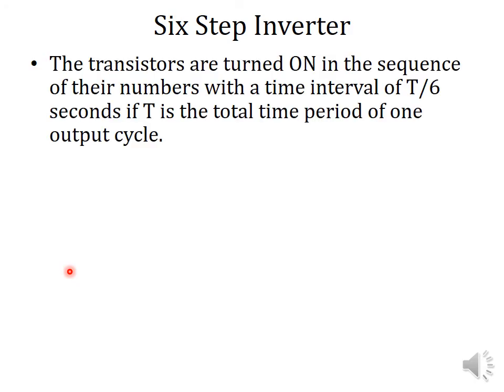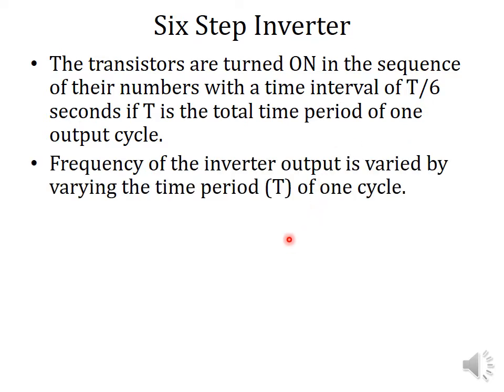If we operate as a six-step inverter, the transistors are turned on in the sequence of their numbers with a time interval of T/6, where T is the total time period of one cycle. The frequency of the inverter output is varied by varying the time period T. The six-step inverter is capable of controlling the frequency of the output voltage only.